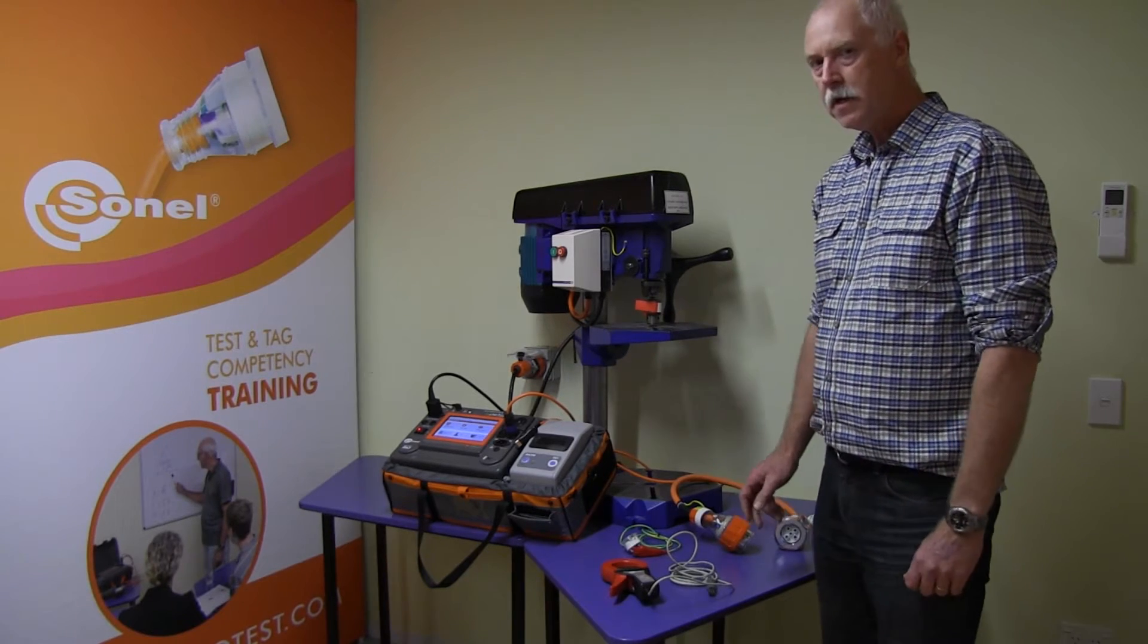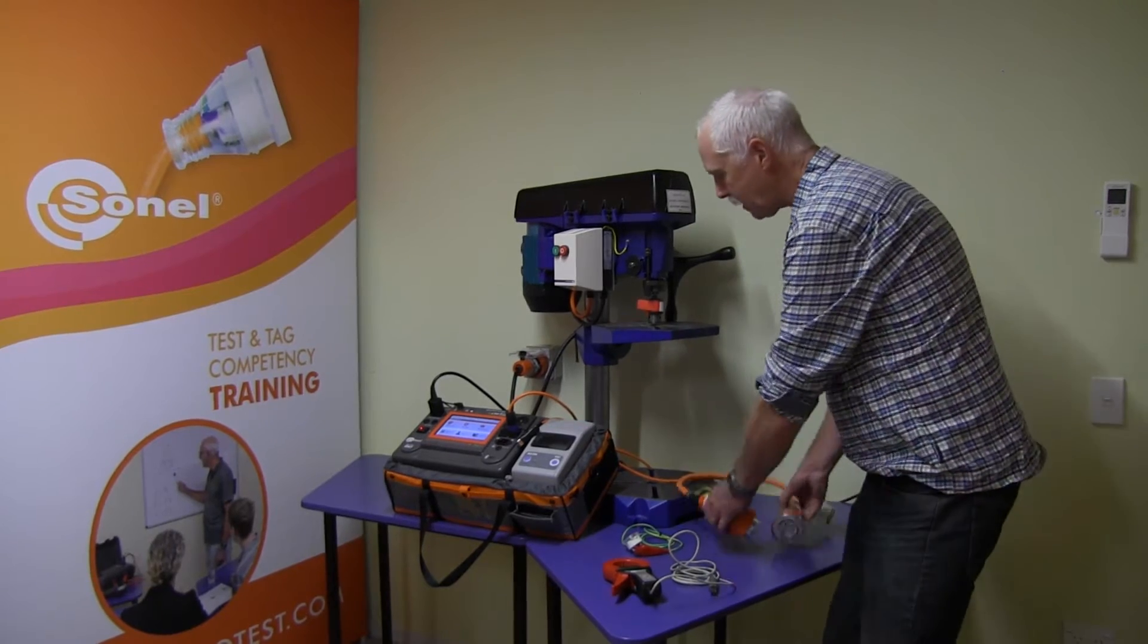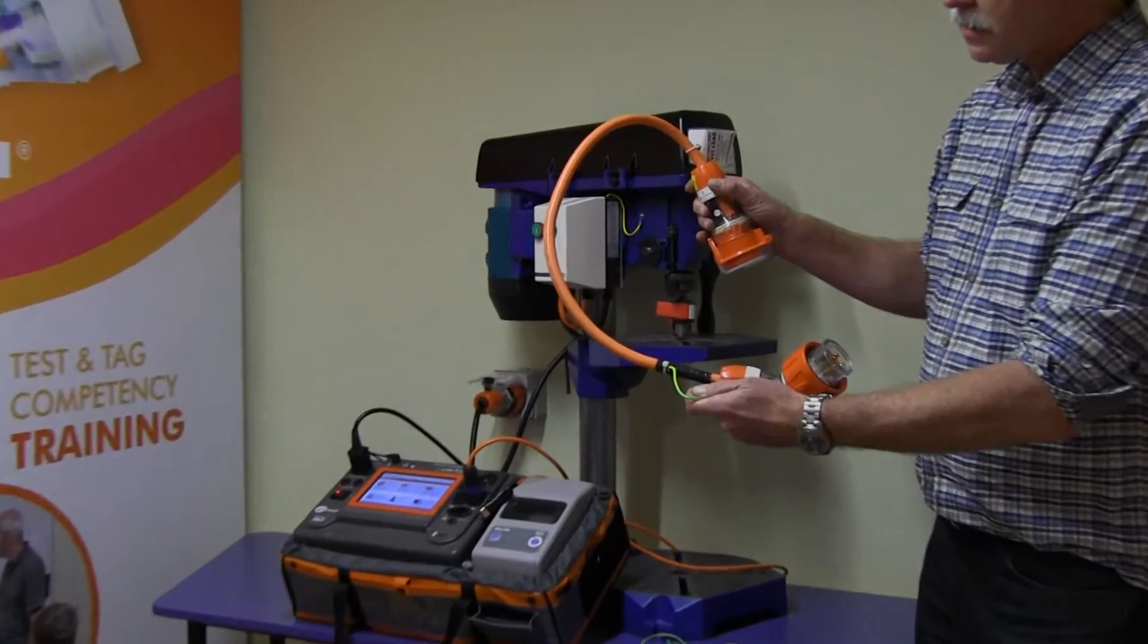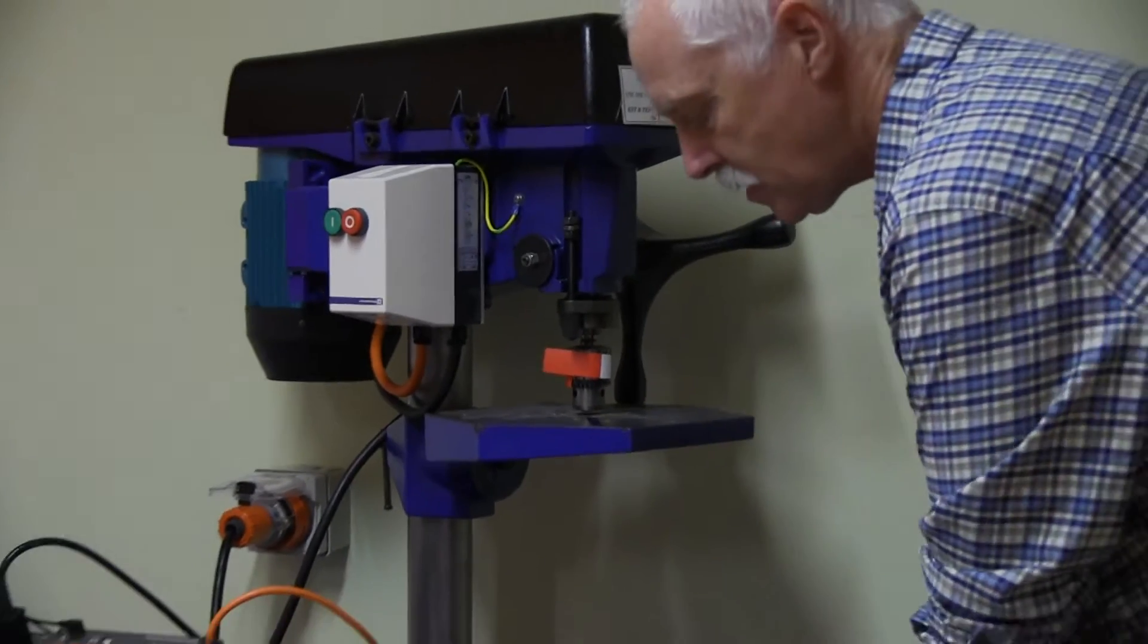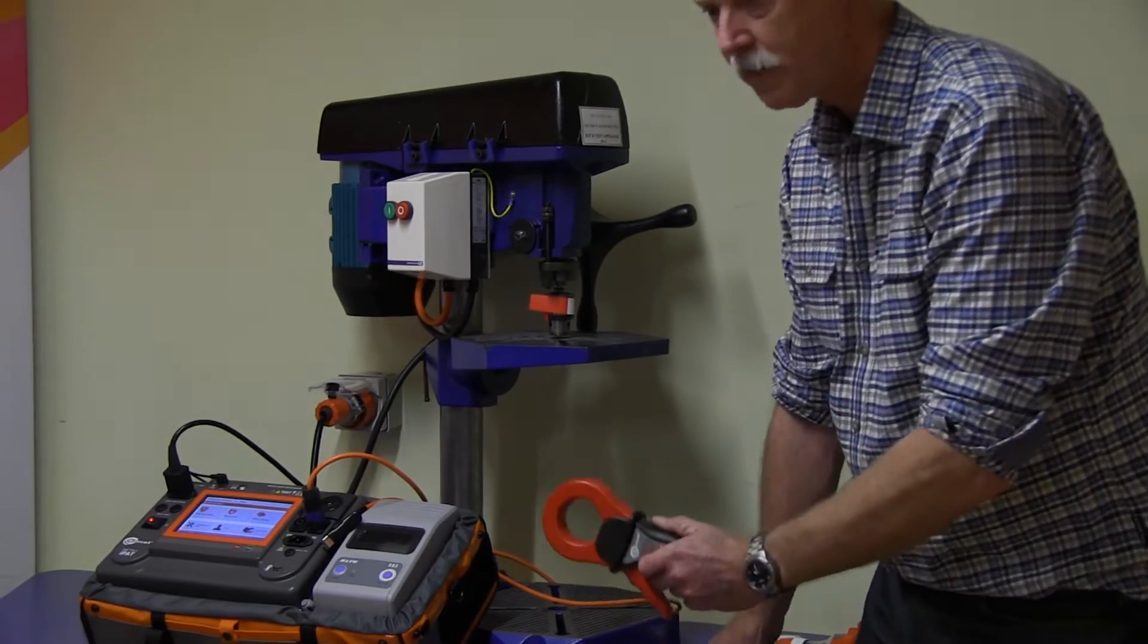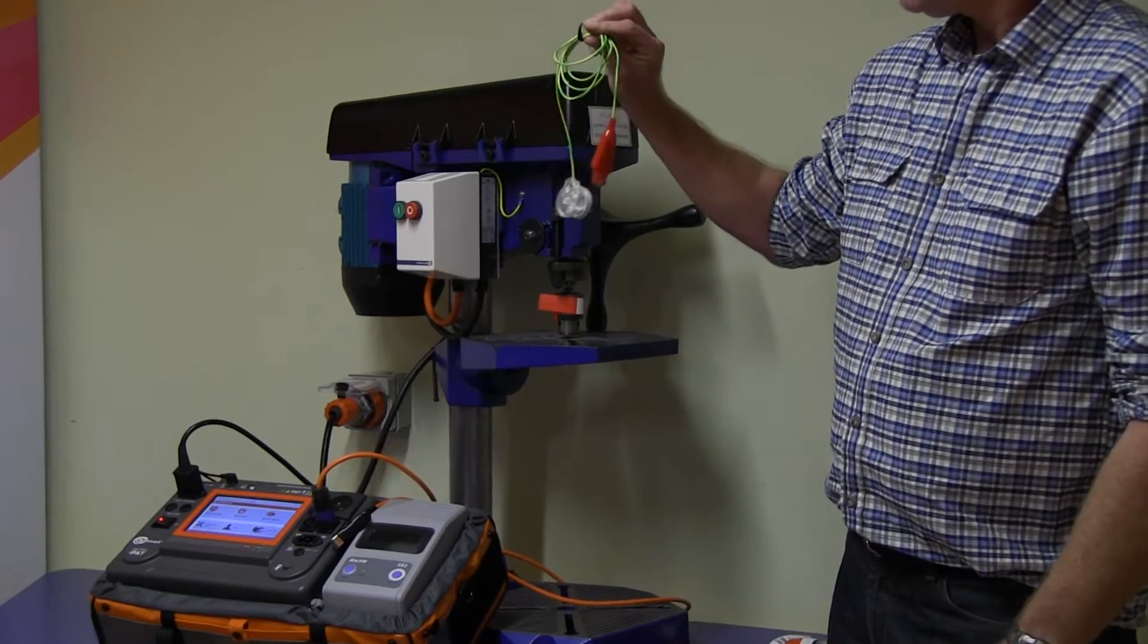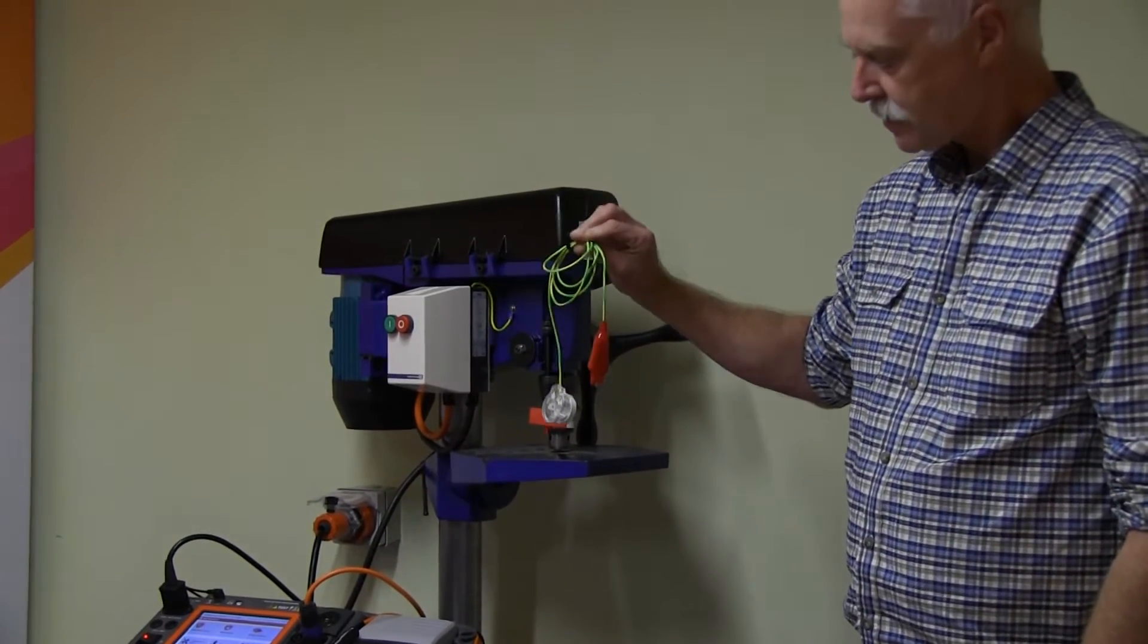To do that we need a suitable PAT tester, an adapter lead with the earth separated out, a clamp that will measure leakage around the adapter lead, and an extra earth wire. I'll set this up now and then we'll be back to do the testing.